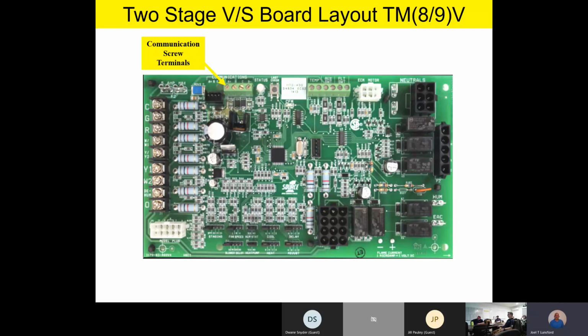You can set this up with our communicating thermostat and just bring 4 wires down from the thermostat and hook it up to your communicating terminals, and then communicating 4-wire going outside to like a 19 SEER product. So this control board is literally compatible with anything in our inventory. You can hook this furnace up to anything in our inventory except the momentum unit, which requires the modulating control that we typically have you hook it up with. But as far as anything else, the 19 SEER all the way down to 13 SEER, you could hook this thing up. Works very, very well.